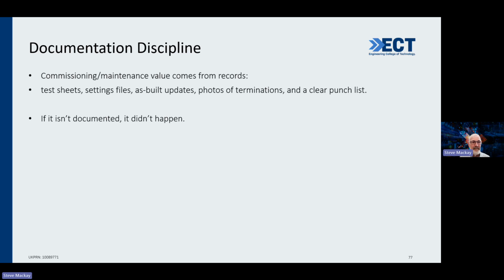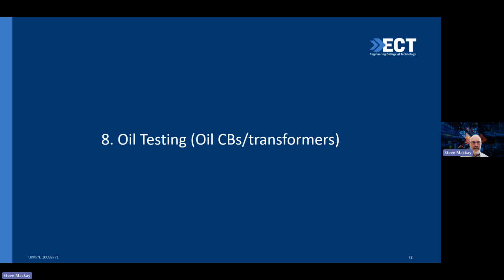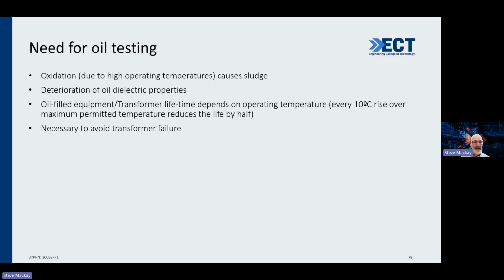Commissioning maintenance, value comes from records. Obviously, test sheets, really important. And obviously, as I said at the beginning of this presentation, if it isn't documented, it didn't happen. So documentation, very, very critical. And you experts out there would be very familiar with bad documentation. Oil testing, obviously is a need because of oxidation and obviously deterioration of oil dielectric properties over time. And you're looking at switchgear as well as transformers.